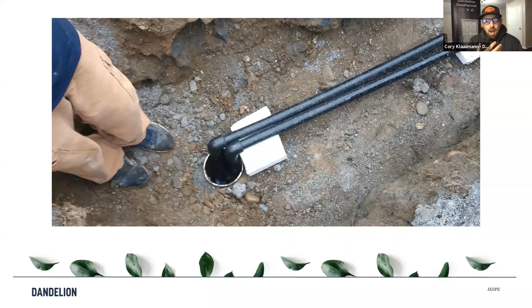Next slide please. From there, we're going to bring the geothermal lines right into the basement. We'll cut a hole in the foundation, seal it up, reinforce it. Before we bury the lines, we'll pressurize the geothermal ground loops to make sure the integrity of that line is true. We don't want to bury the lines and have a leak at any of the connection points, so we leave it pressurized. If it doesn't drop in pressure, we'll go ahead and bury the lines, and we do so with the expectation to really never have to go back and dig them up again.